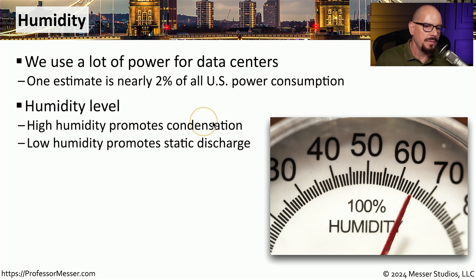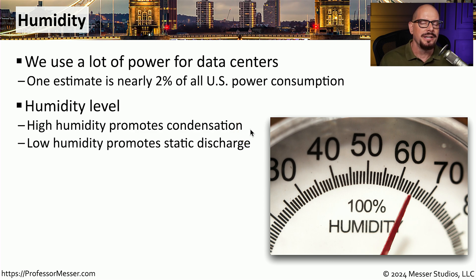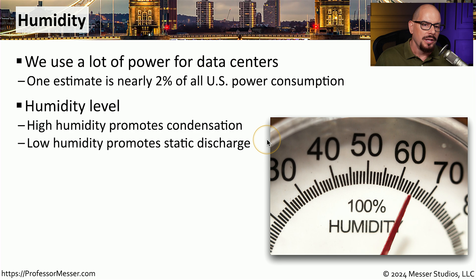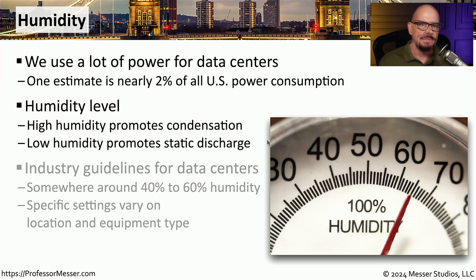Managing humidity in a data center can be a bit of a challenge. If you have high humidity, then you've got condensation, and having any type of water in a data center is never a good idea. If your humidity is too low, you could have excessive static discharge, which is also potentially harmful to the equipment.